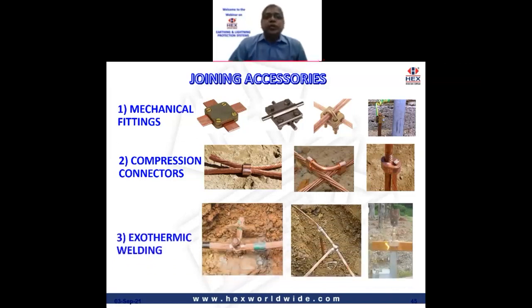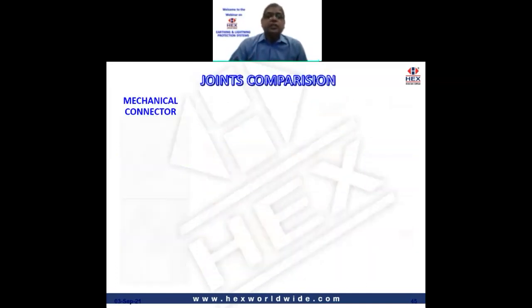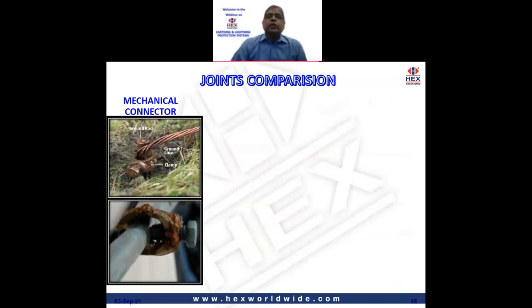Now, which is good, which is bad from this? Once again, there has been a study. Let us see what it is. First of all, let's have a look at this. Let us compare the three types of joining accessories. Whereas the mechanical fittings are fitted using screws or bolts, there are a lot of air gaps, as can be seen, which is not desirable in any electrical connection. And this leads to failure of joints.